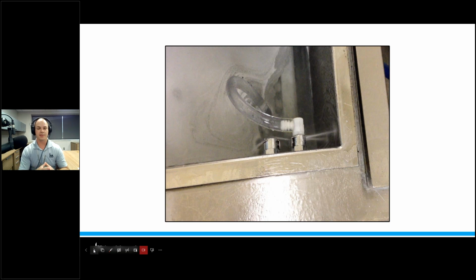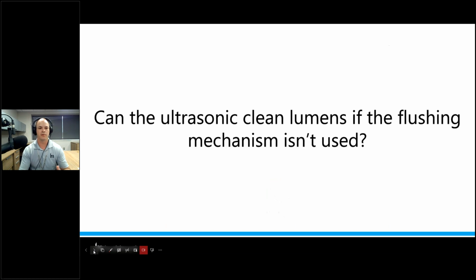So case study number 3, we have a failed soil removal test for lumen, and this is the ultrasonic that we were using. Just as an FYI, we have this service panel open. Hopefully you're noticing right away, this is the generator. The generator likely has nothing to do with the lumen cleaning function, but it is something to be aware of and see that, hey, that's different than the one I showed you earlier.